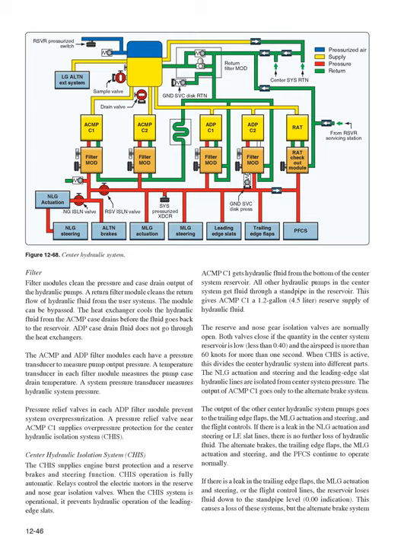The ACMP and ADP filter modules each have a pressure transducer to measure pump output pressure. A temperature transducer in each filter module measures the pump case drain temperature. A system pressure transducer measures hydraulic system pressure. Pressure relief valves in each ADP filter module prevent system overpressurization. A pressure relief valve near ACMP C1 supplies overpressure protection for the center hydraulic isolation system, CHIS.